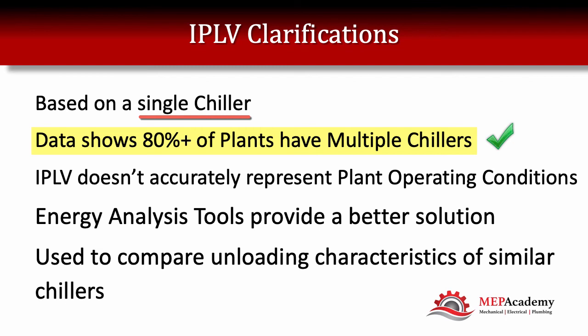IPLV is used to compare unloading characteristics of similar chillers. It's a simple calculation using the EERs at 25%, 50%, 75%, and 100% load — four points plugged into a formula to get the part load value. The chiller is sized for 100% load, which is the worst condition, but it will rarely see that — maybe one or two days a year. Most of the time it runs at part load. IPLV is also part of ASHRAE 90.1.